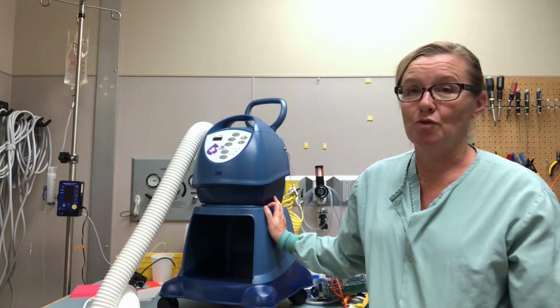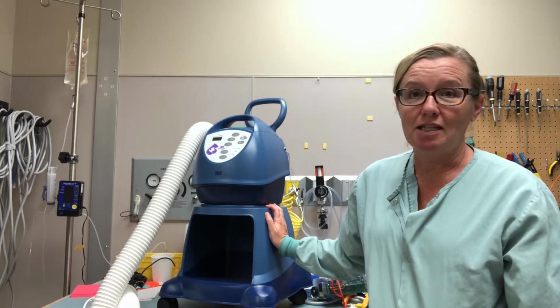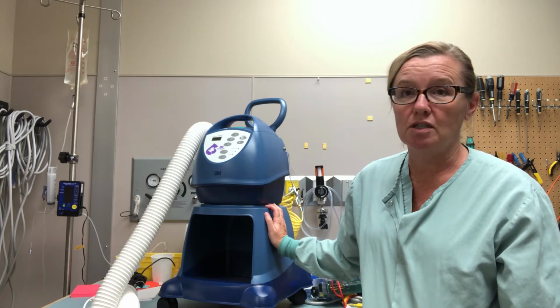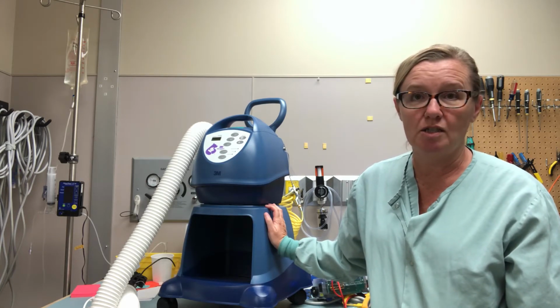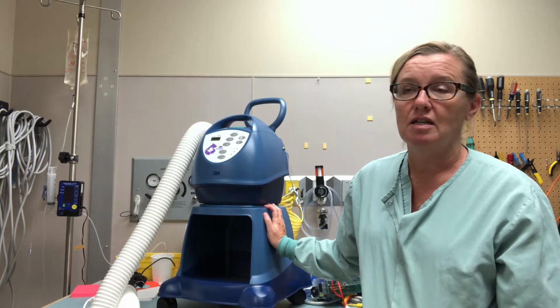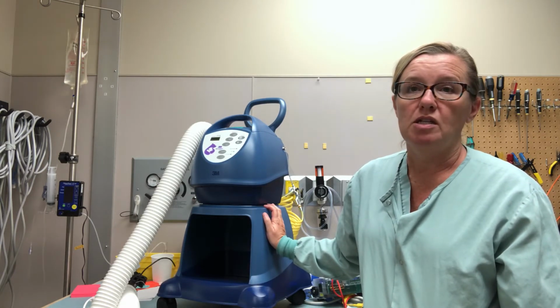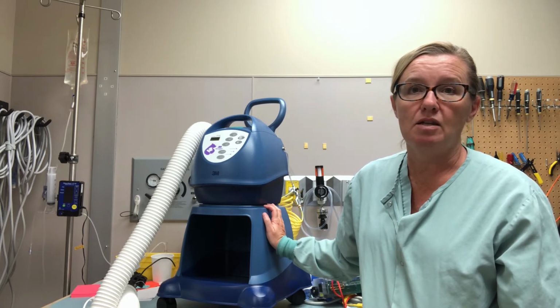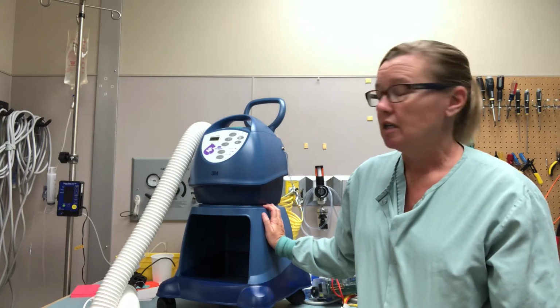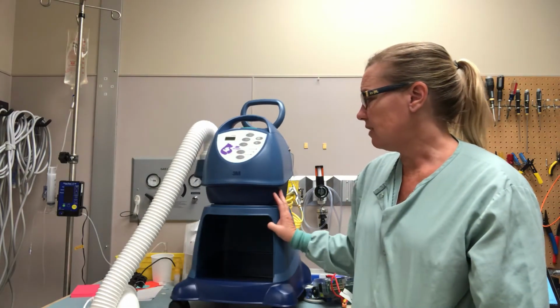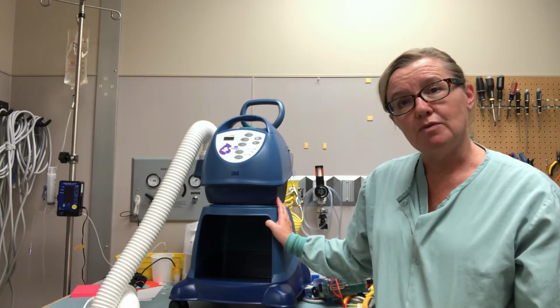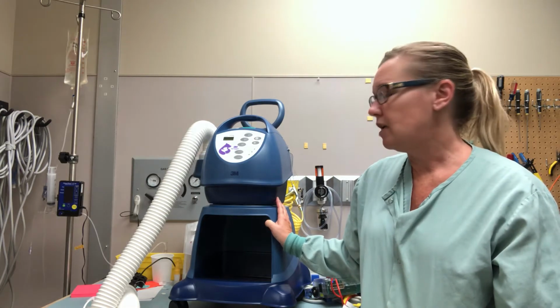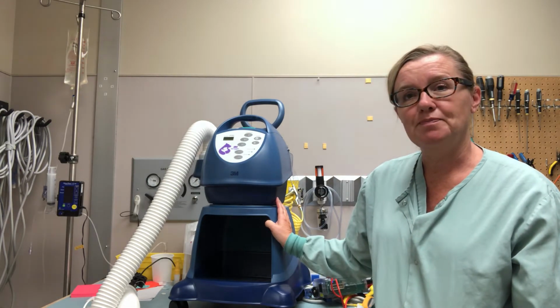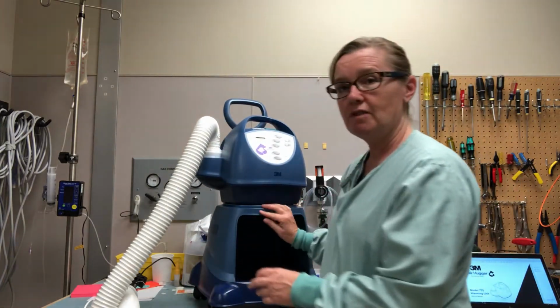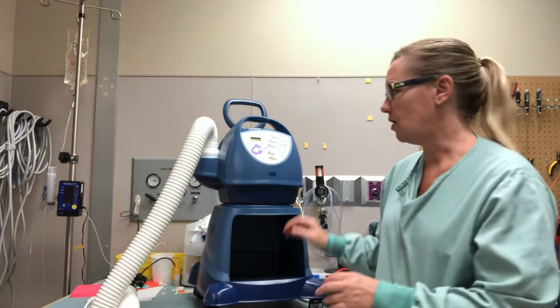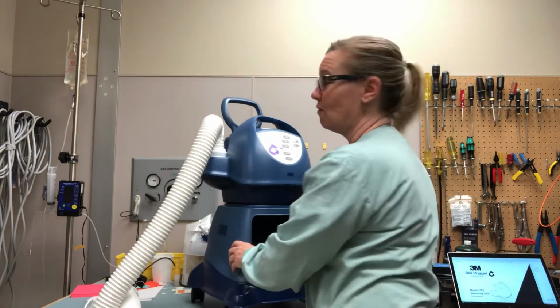Most rooms in the hospital get pretty dusty. These can run for several hours. They're used a lot in surgical areas, pre- and post-surgical areas, ICUs, anywhere where the patient needs help maintaining their body temperature. So even though it says the filter is every 12 months, we check it every 6 months. To check it, the filter is underneath the Bair Hugger here. So I'm going to turn it over.